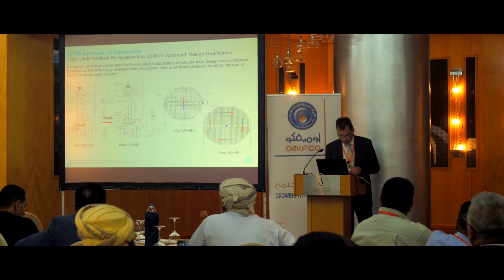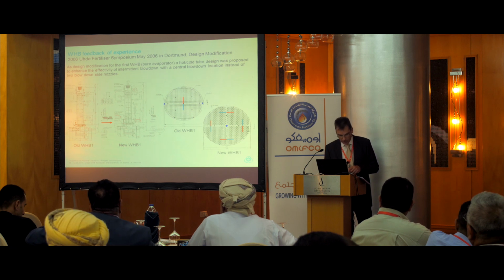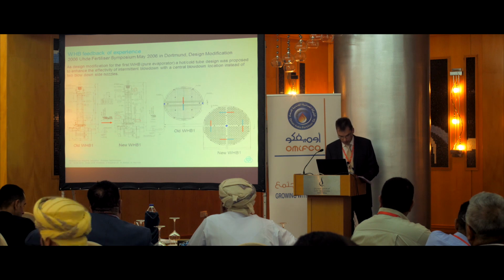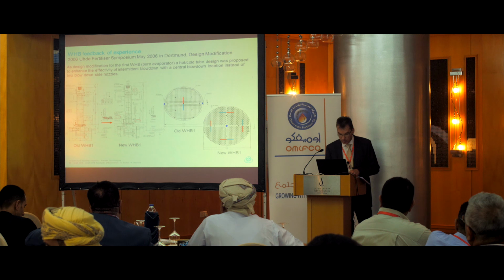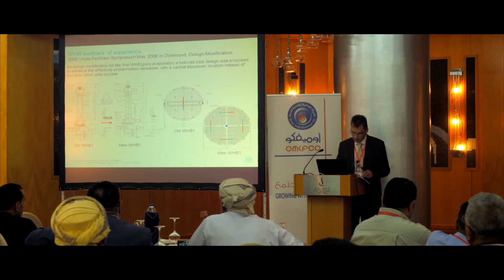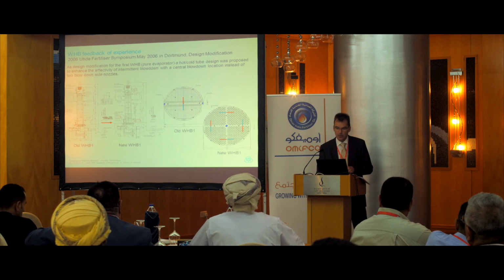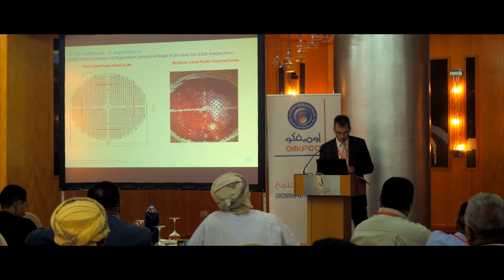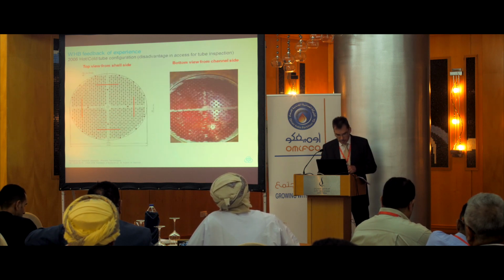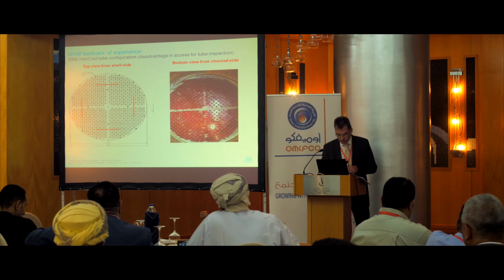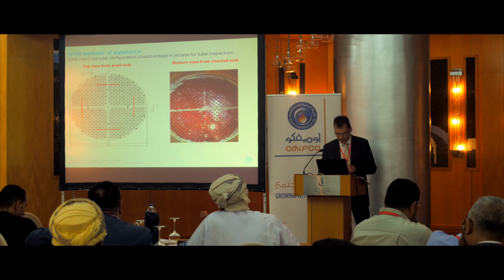All these modifications had the target to improve the blowdown based on experienced corrosion damages under deposits. But this hot and cold design has not been perfect and needed some modifications. I will show why it was not perfect. The hot-cold design as shown here on the slide has a disadvantage for inspection of tubes and also for identification of leaking tubes in case of a leak.